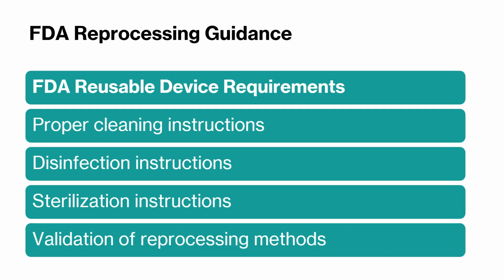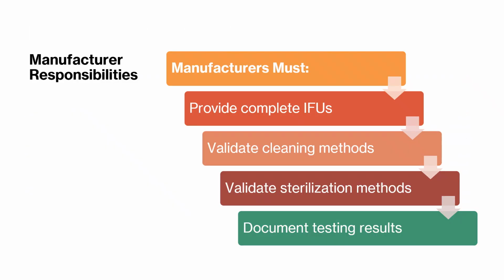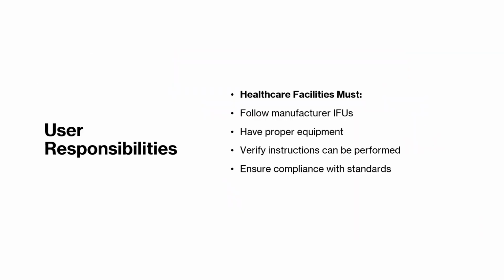The FDA requires manufacturers of reusable medical devices to provide detailed instructions for cleaning, disinfection, and sterilization. These instructions must be validated to ensure the device can be safely reused. Manufacturers are responsible for developing and validating reprocessing instructions and ensuring that healthcare facilities can safely prepare the device for reuse. Healthcare facilities and CS professionals are responsible for following the manufacturer's instructions and ensuring they have the necessary equipment and resources to perform reprocessing correctly.